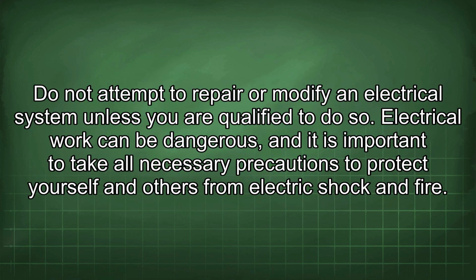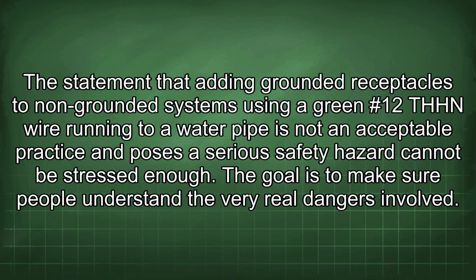Do not attempt to repair or modify an electrical system unless you are qualified to do so. Electrical work can be dangerous, and it is important to take all necessary precautions to protect yourself and others from electric shock and fire. The statement that adding grounded receptacles to non-grounded systems using a green #12 THHN wire running to a water pipe is not an acceptable practice and poses a serious safety hazard cannot be stressed enough. The goal is to make sure people understand the very real dangers involved.